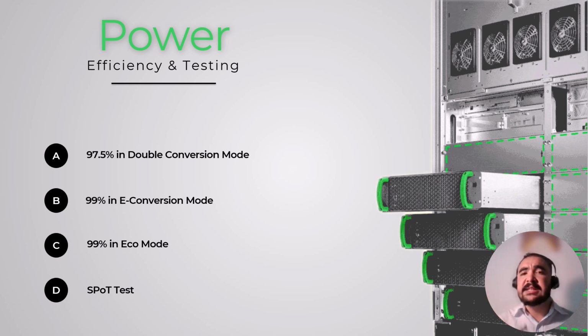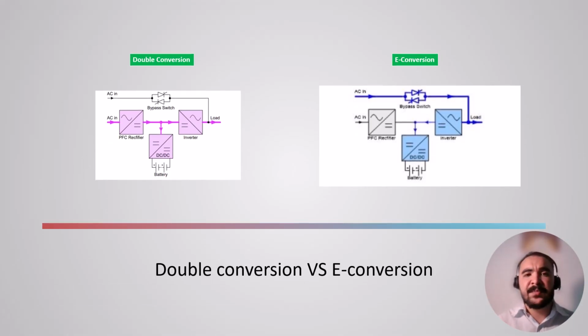Let's do a fast recap on what is e-conversion and double conversion, just to let you understand what the main difference between them is. In order for me to differentiate and benchmark between these two topologies, I'll have first to go back to the traditional setup, check how it works, then we can differentiate between it and the new e-conversion setup. With the double conversion, it's well known that the alternate current will come from the grid. It will go all the way through the rectifier, where we'll have the first operation: power factor correction, harmonic filtration, voltage and frequency regulation, and finally switching from alternate current to direct current. It continues its path, charging the batteries, then goes to the inverter, where it will be switched back from the direct current to alternate current and transmitted immediately to the load.